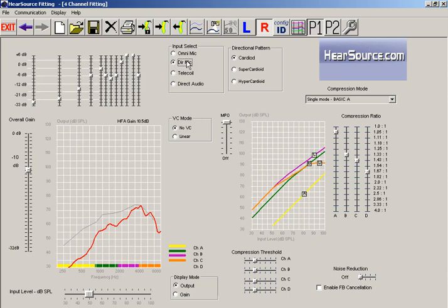The way the directional microphone system works is, once it's turned on, it's going to give you about a 45 degree field of input wherever you're looking. So the signal has to be in front of you. Now any sounds that are occurring outside this field, usually from the sides or behind you, the hearing aid is not going to pick up those sounds as loudly.